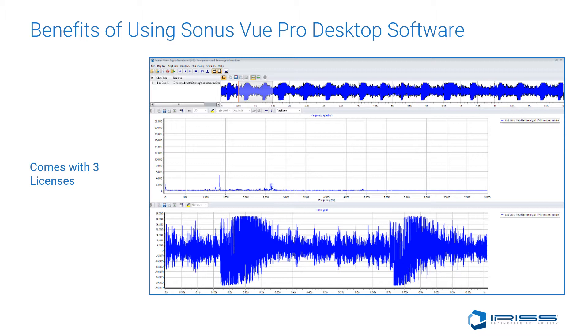Sound analysis can even be used to determine whether an electrical fault is corona, treeing, tracking, arcing, partial discharge, phase variant, loose windings, or delamination of windings in electrical assets. These events all have distinct fault signatures in a time signal domain.